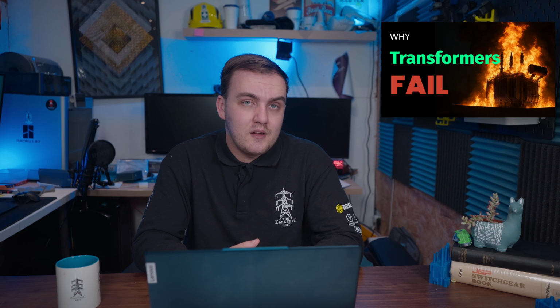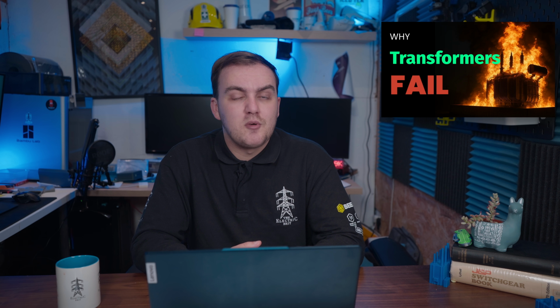Like transformers, they also have bushings which, if oil filled, can also fail, but at these lower voltage it's unlikely to be oil filled. You can check out the video up here on why transformers fail, which I produced in response to my video on North Hyde being taken down, so you can be more informed the next time someone tells you it was foul play. As you can see, the majority of these things come down to lack of maintenance, with some coming down to design or pure chance. But until the full report comes out, we won't know for sure.